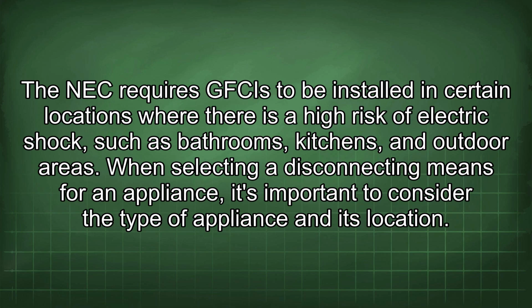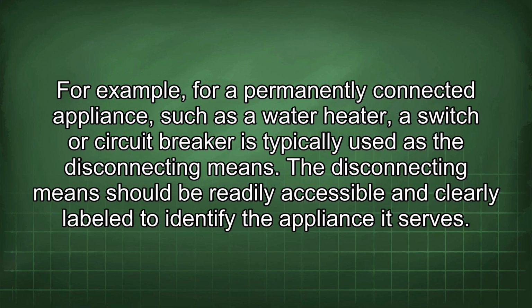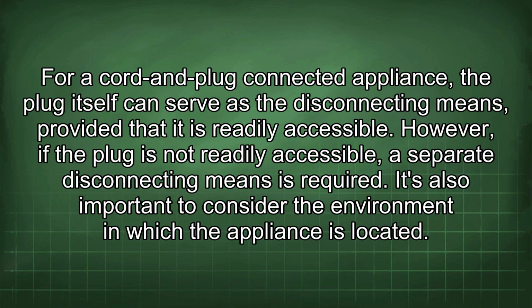When selecting a disconnecting means for an appliance, it's important to consider the type of appliance and its location. For example, for a permanently connected appliance, such as a water heater, a switch or circuit breaker is typically used as the disconnecting means. The disconnecting means should be readily accessible and clearly labeled to identify the appliance it serves. For a cord and plug connected appliance, the plug itself can serve as the disconnecting means, provided that it is readily accessible. However, if the plug is not readily accessible, a separate disconnecting means is required.